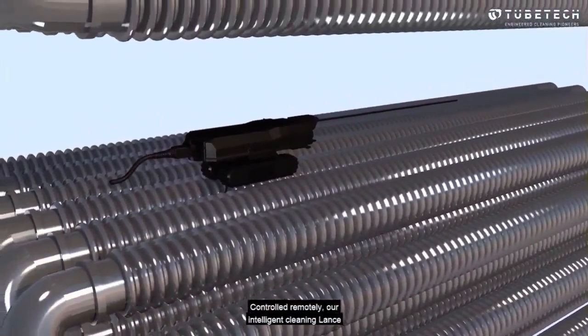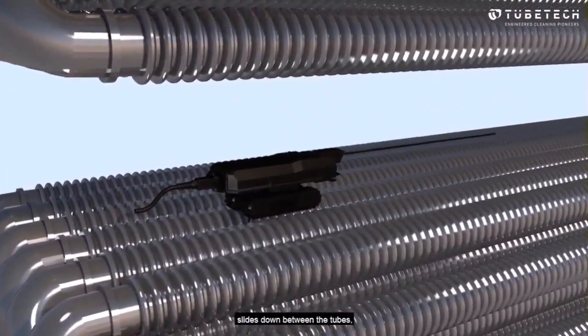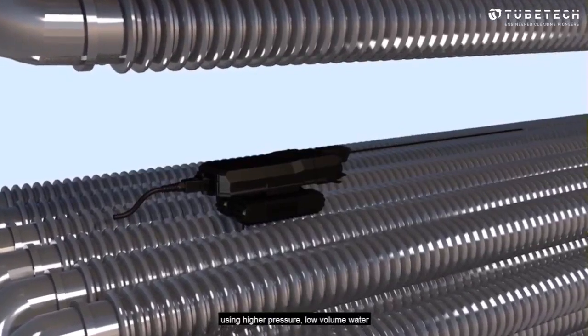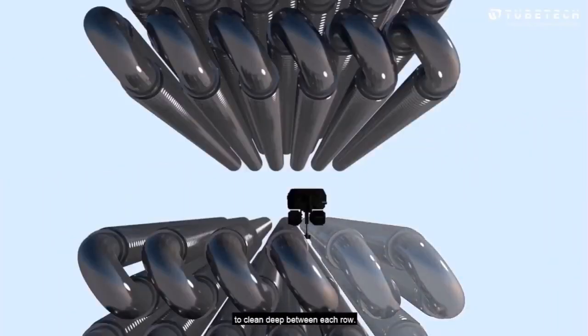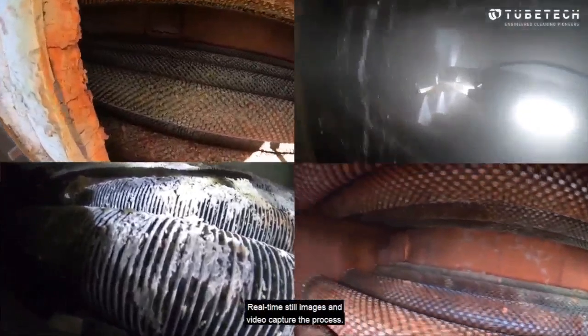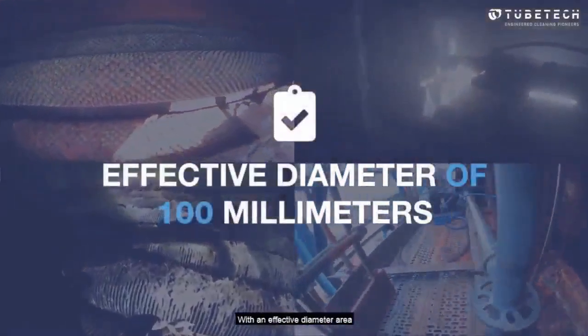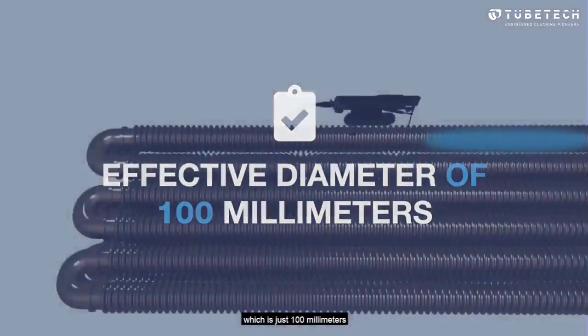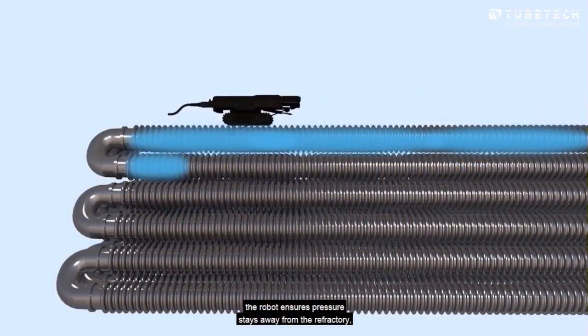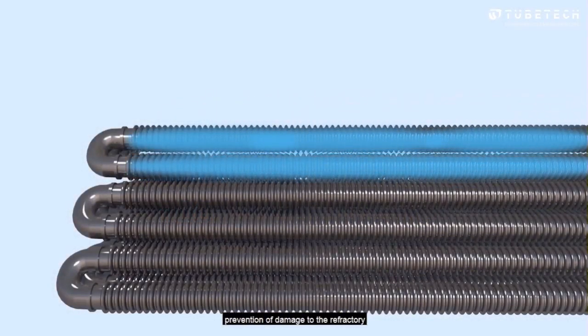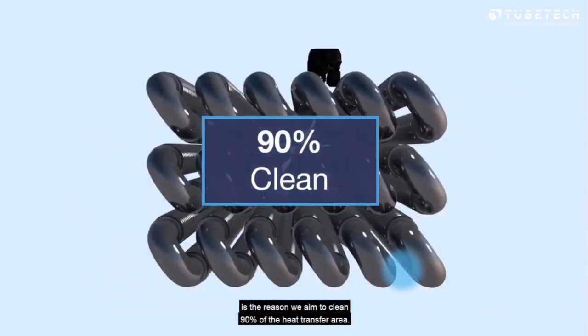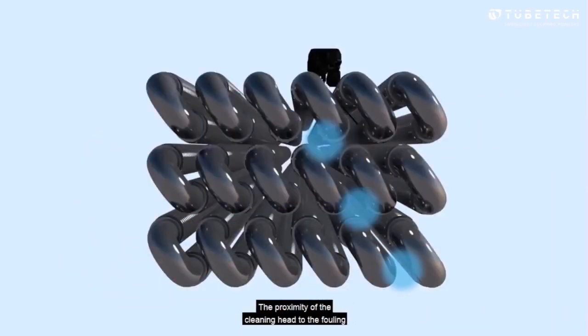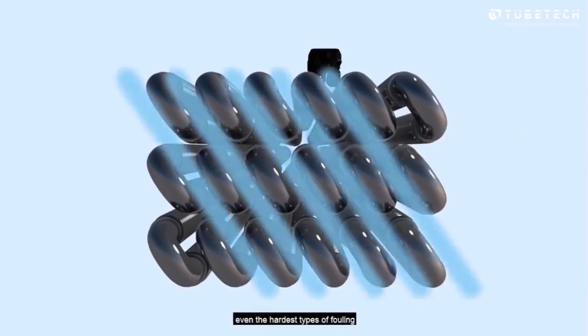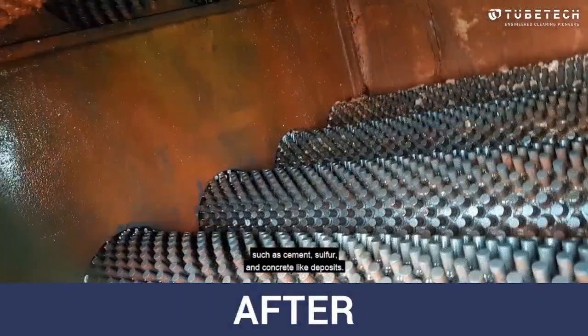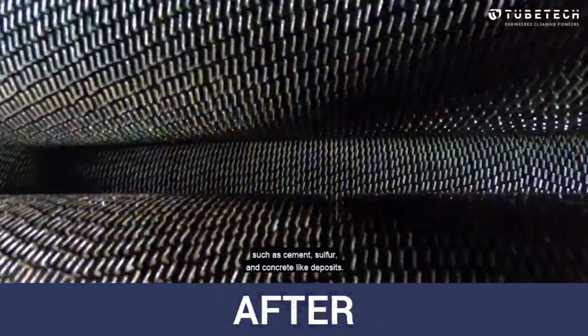Controlled remotely, our intelligent cleaning lance slides down between the tubes, using high-pressure, low-volume water to clean deep between each row. Real-time still images and video capture the process. With an effective diameter area of just 100 millimeters, the robot ensures pressure stays away from the refractory. Prevention of damage to the refractory is the reason we aim to clean 90% of the heat transfer area. The proximity of the cleaning head to the fouling means that it easily removes even the hardest types of fouling, such as cement, sulfur, and concrete-like deposits.